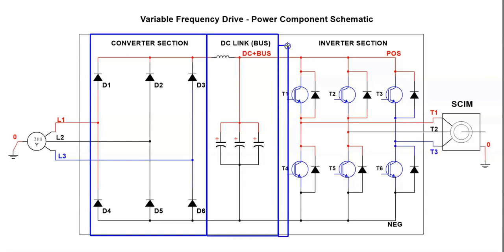The last section converts the DC current back to AC. And we do that so that we can control the frequency and the voltage applied to the motor, using volts per Hertz or scalar mode depending on which manufacturer you're talking about. It's doing the same thing though. We're using six transistors, and the firing sequence of the transistors and the timing determines the direction of the motor and the speed and so on.